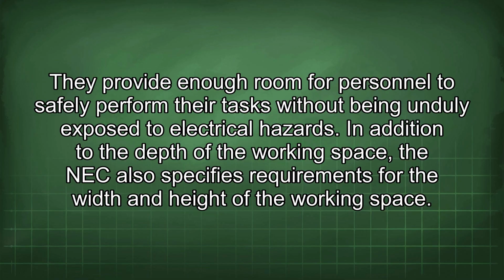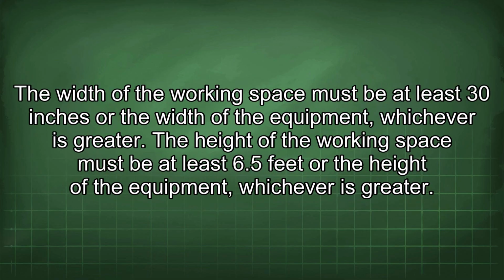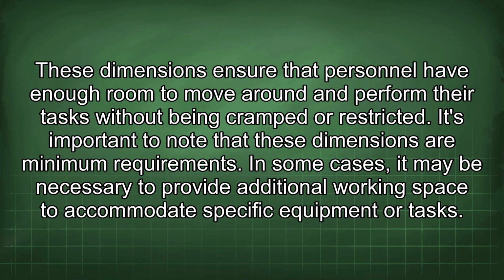In addition to the depth of the working space, the NEC also specifies requirements for the width and height of the working space. The width of the working space must be at least 30 inches or the width of the equipment, whichever is greater. The height of the working space must be at least 6.5 feet or the height of the equipment, whichever is greater. These dimensions ensure that personnel have enough room to move around and perform their tasks without being cramped or restricted.